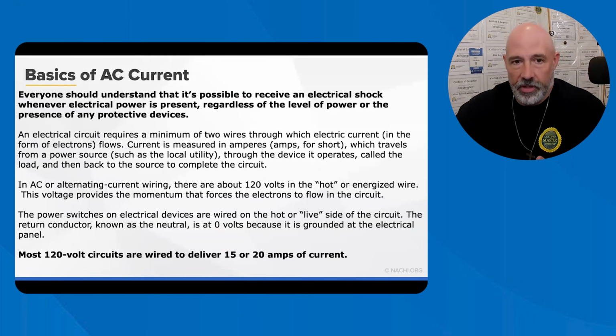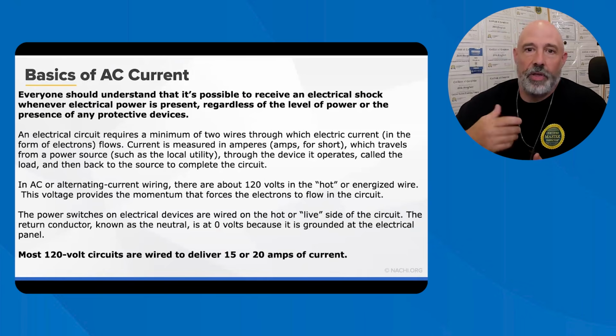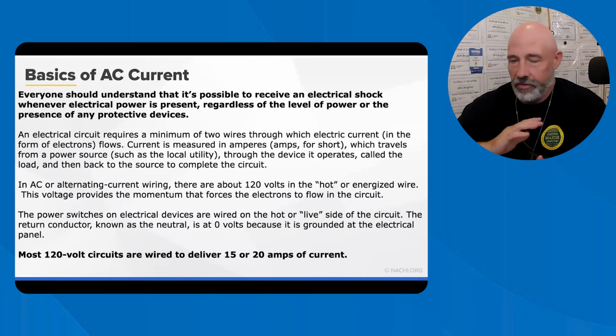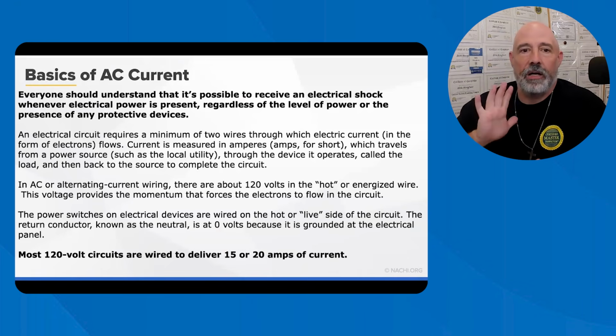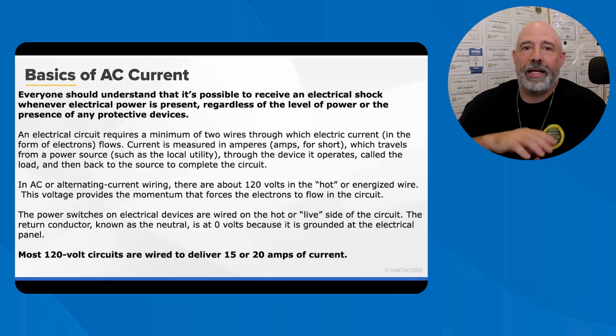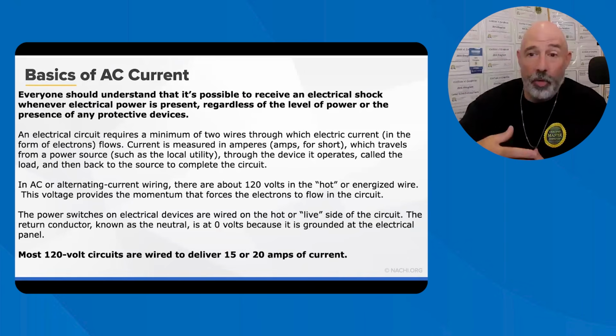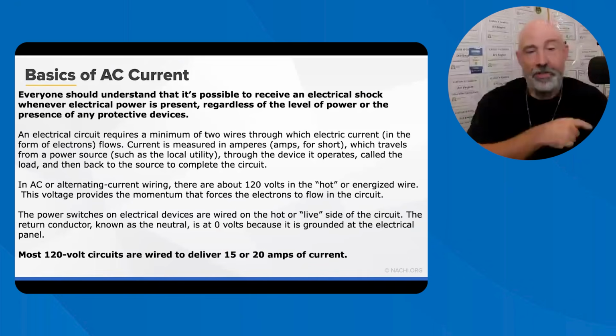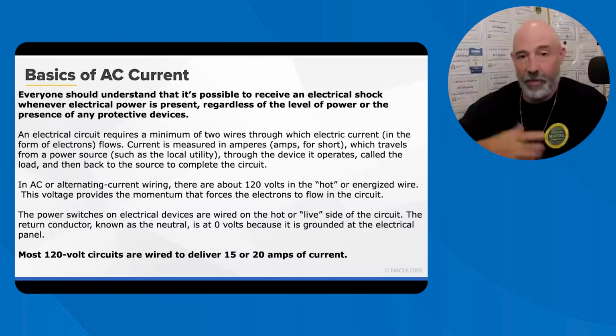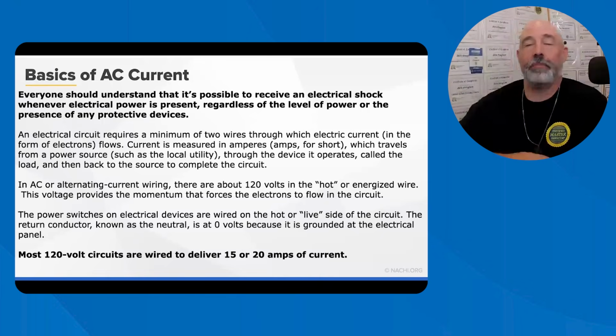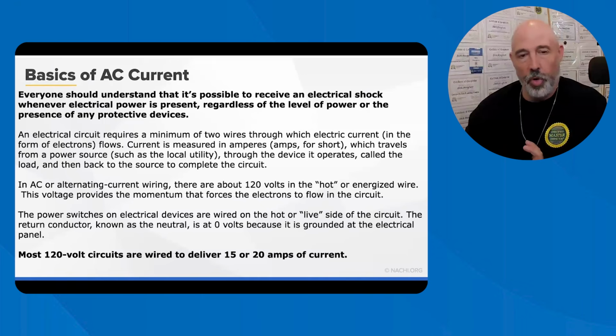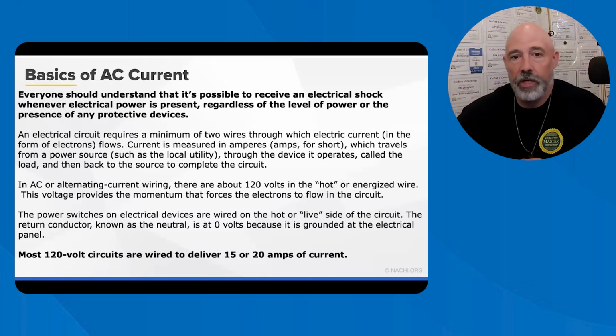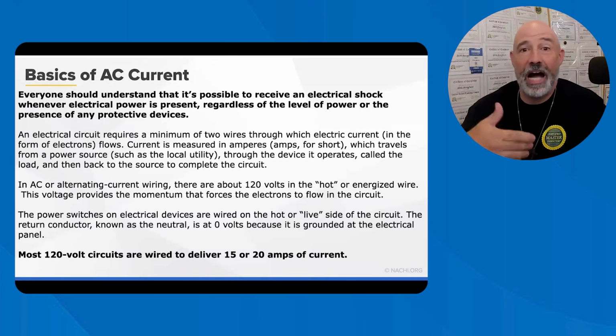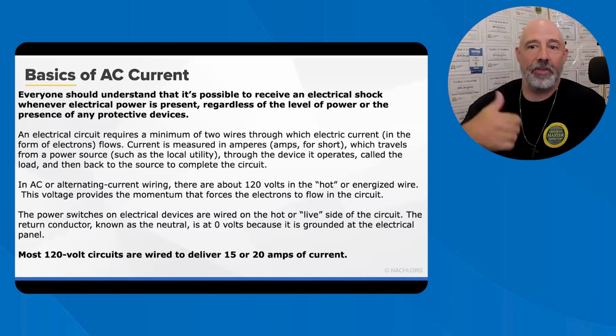So, electrical shock hazards. Electrical shock is possible anytime power is present, regardless of the voltage or system devices. A typical electrical circuit has a conductor that delivers power to the load and the neutral conductor that returns the current to the source. That completes the circuit. You remember in third or fourth grade, when you took the battery and hooked up the light, that's exactly what's happening. But this is much more electricity than a 9-volt battery or a 1.5-volt battery. Most residential circuits operate at approximately 120 volts and carry either 15 or 20 amps.